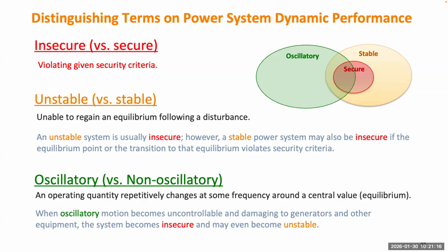But there could be cases where some new equipment is placed on the power system and the engineers have not fully understood this new equipment, such as inverter-based renewable resources. They need to do a more stability study. So it could be possible, but even that's not very often. If this new equipment can cause some new stability issues which are not fully understood, then if they operate this equipment based on the existing reliability standard, they may think the situation is secure, but actually instability may happen. But usually, a secure system has to be stable, okay?